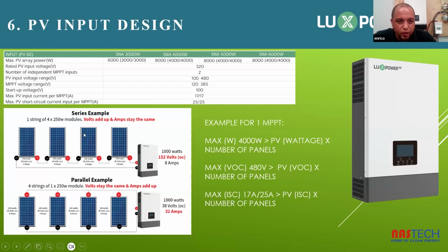So you take your number of panels, this is 1, 2, 3, 4, times your open circuit voltage per panel. Each panel here is 38 volts. So we add those 38 volts, it gives us 152 volts open circuit voltage at 8 amps. So this is a good method in connecting panels, keeping the voltage at a high voltage and a low amperage. So using a combination of these two, you can play around with the configuration, and you can optimize it as much as you would like, or according to your customer's needs.